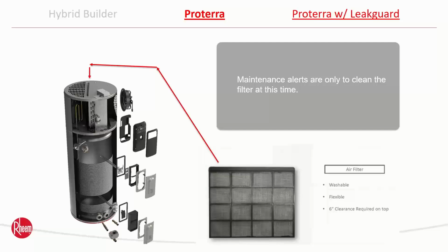Maintenance alerts. Right now, the only maintenance alert we have is for the filter up top, which, as you see right there, is just a screen. It's flexible. Now, we do require 6 inches of space up above the unit minimum so that you can get this filter out. You just pull it out. If you get the alert, it says it's dirty, you pull this filter out, take it under a sink, you're going to run water over it, brush the dirt off of it, dry it out, shake it out, stick it back in. So it's not a one and done filter, it is reusable.